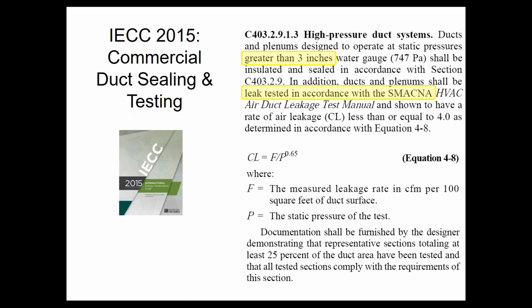So residentially, the duct leakage test requirement kicked in when you had ductwork in an unconditioned space. For commercial, the duct leakage test kicks in when you have a high static system. The higher the static, the higher the pressure, the higher the amount of CFM that will leak out of a given size hole.